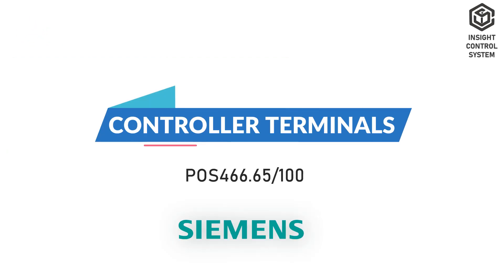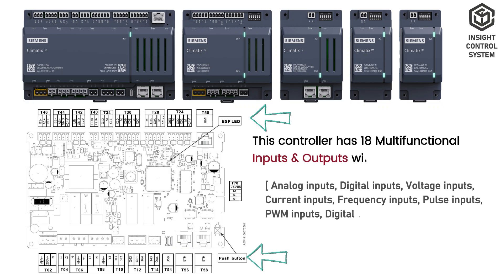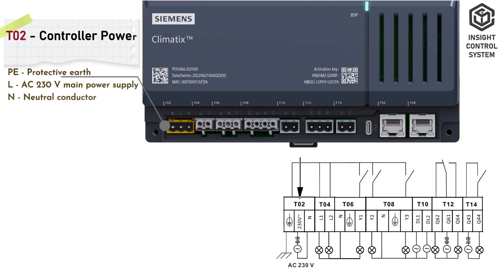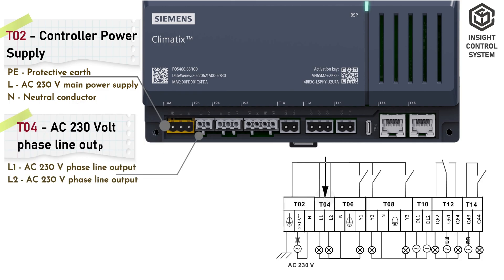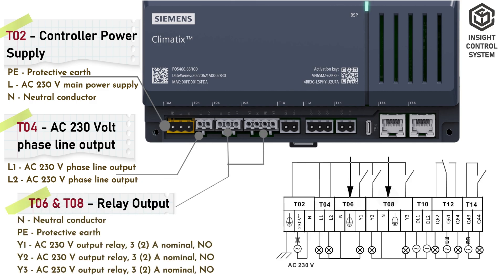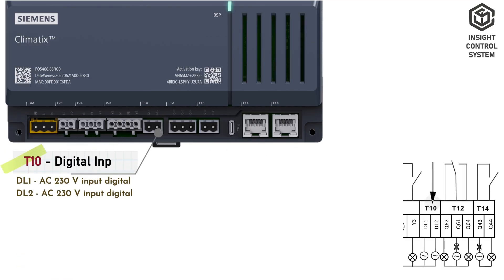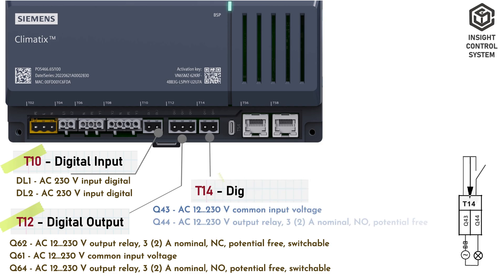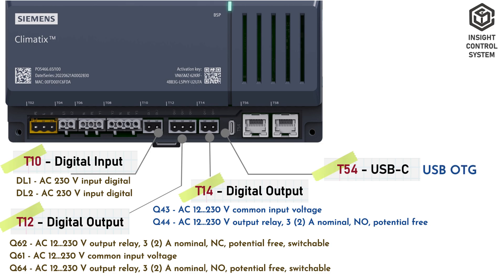Controller Terminals: This controller has 18 multifunctional inputs and outputs with various signal types. Terminal T2 is the controller power supply. Terminal T4 is AC 230 volt phase line output. Terminal T6 and T8 are relay outputs. Terminal T10 is digital input. Terminal T12 is digital relay output for potential-free relays and switchable.